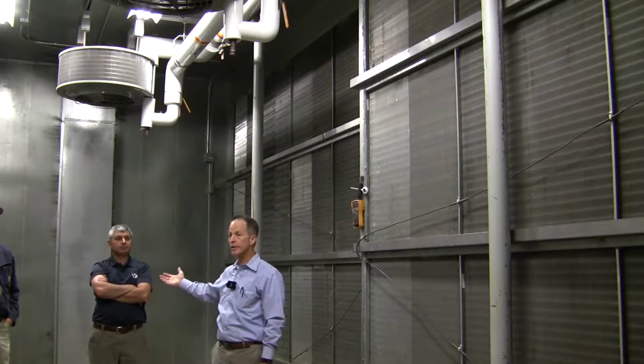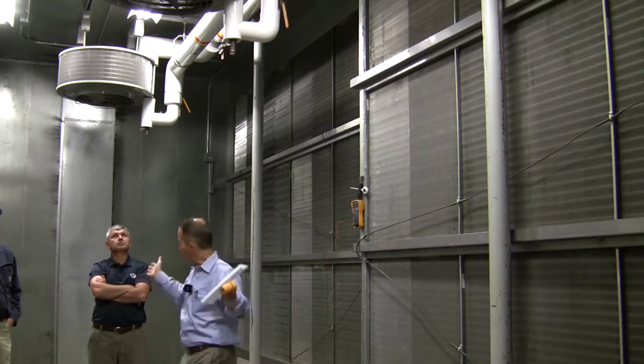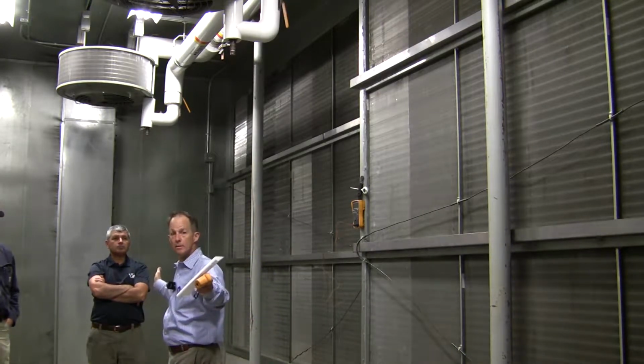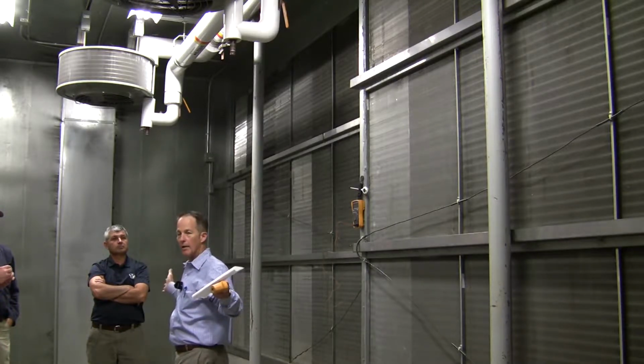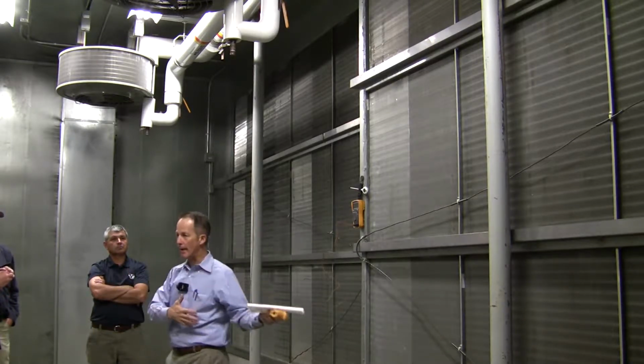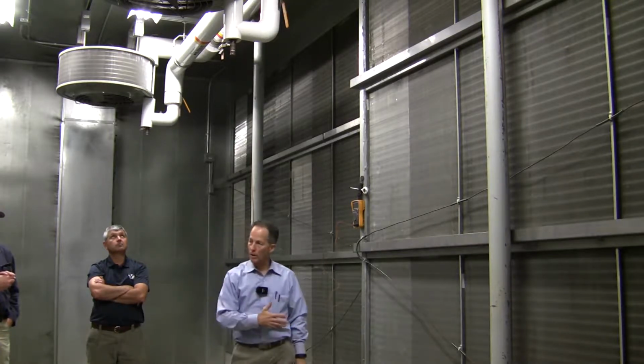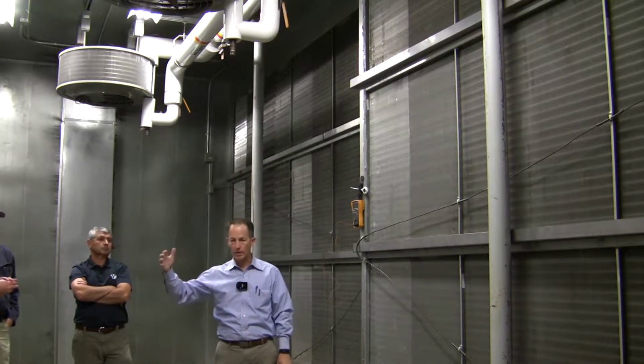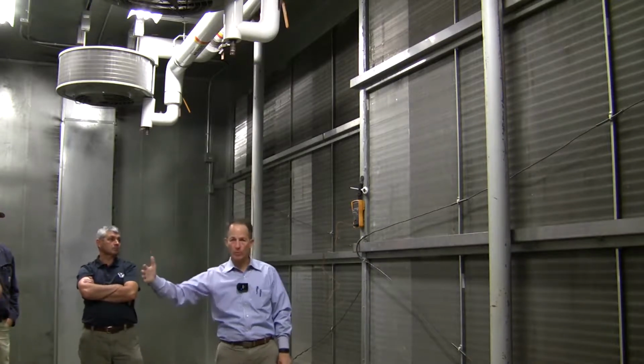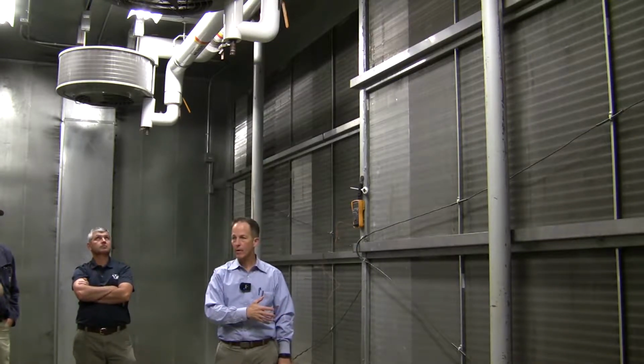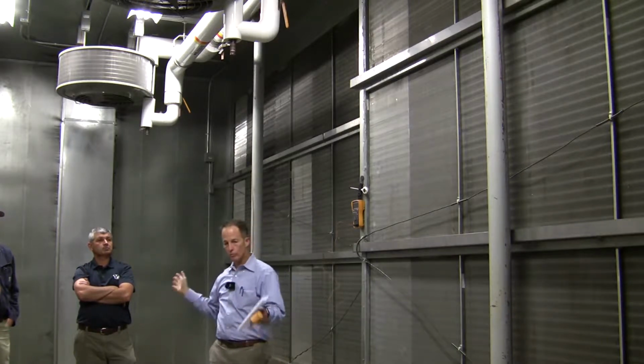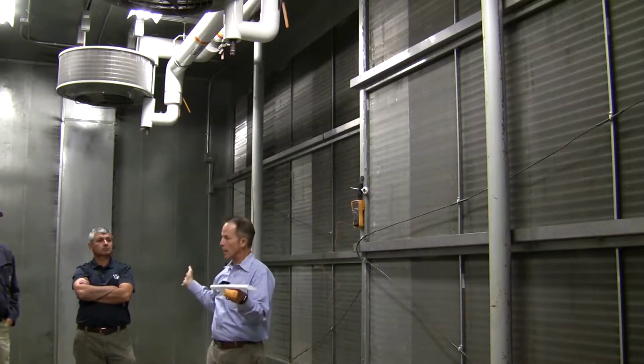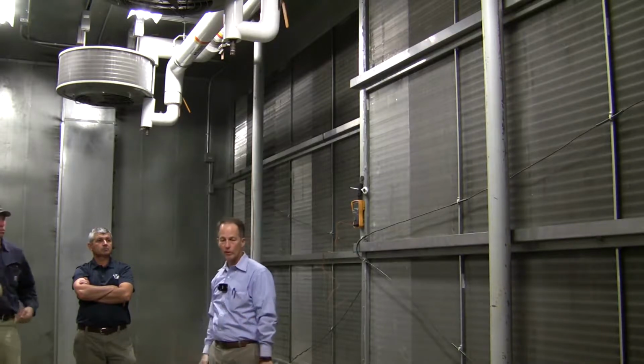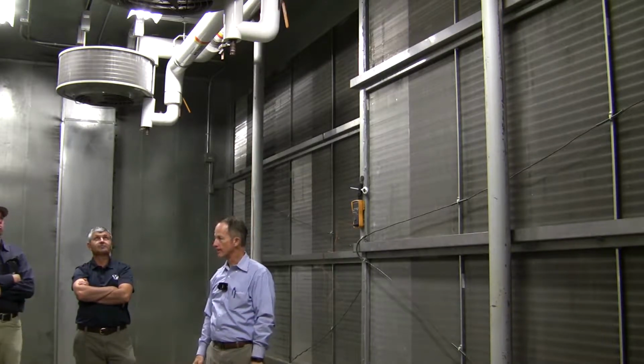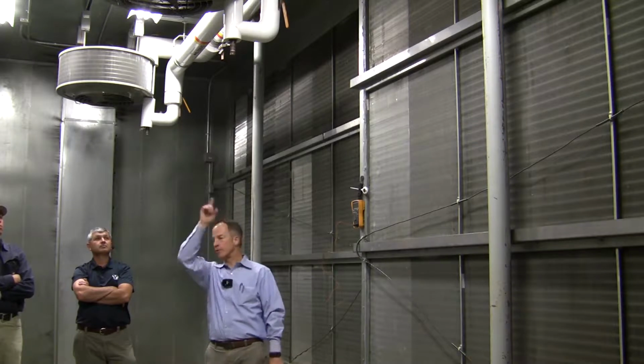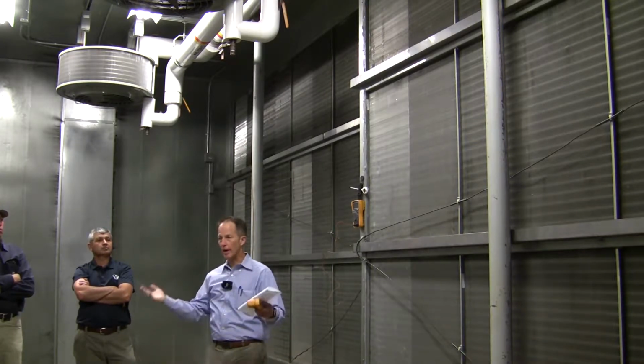Static pressure is the resistance. If I have a big coil sitting here and I'm not able to bypass that, then the fan all winter or all summer long is pulling and using energy to pull air through the coil. By putting these up here, you eliminate that static pressure drop across the coil and save energy over the life of the fan. Now, this doesn't mix very well though, so it's a trade-off.